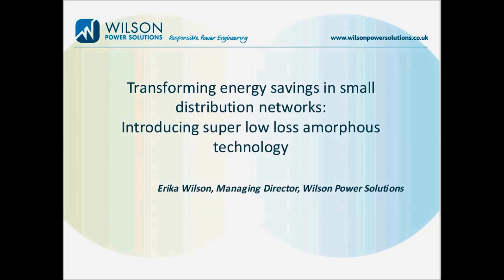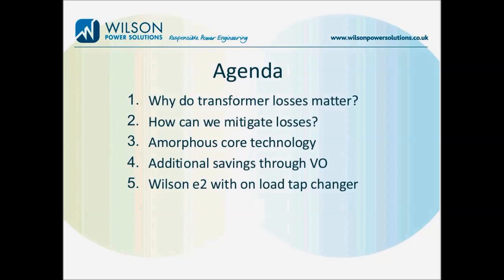Looking at the agenda for today, firstly, why do transformer losses matter at all, and how can we mitigate these losses? The amorphous technology behind mitigating those losses, and then of course the additional savings that can be made through the inbuilt voltage management capability of the transformer. And finally, I'll discuss the new Wilson E2 with the on-load tap changer, which addresses fluctuations in the incoming supply voltage at site.